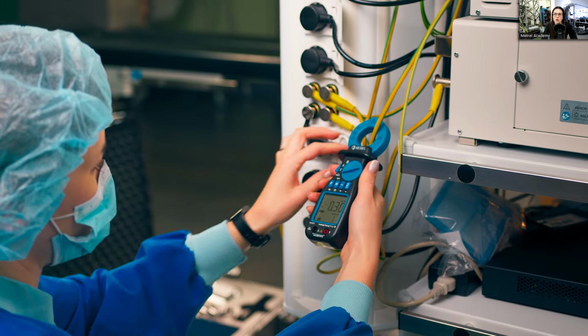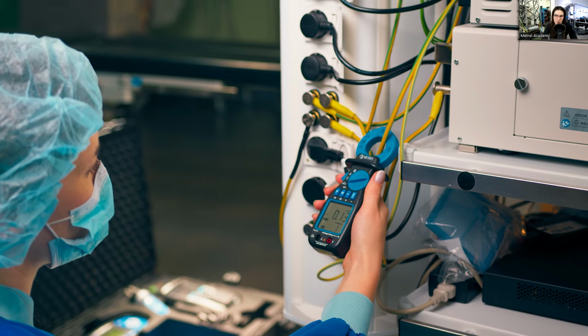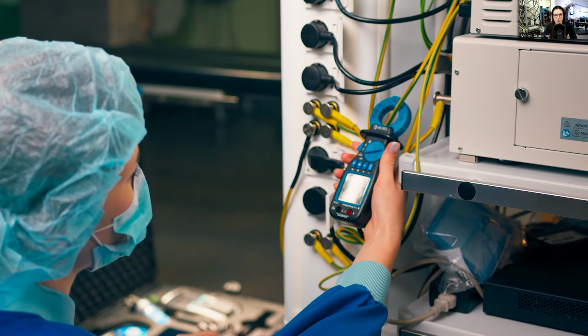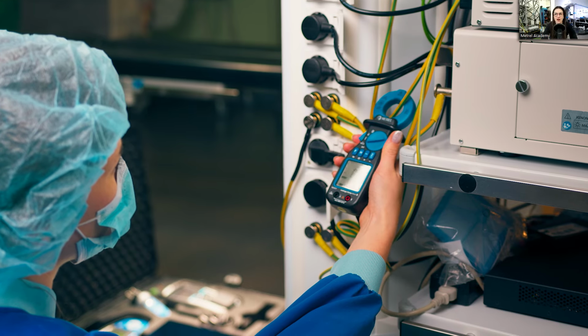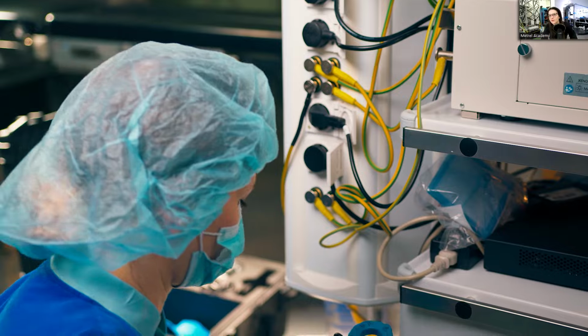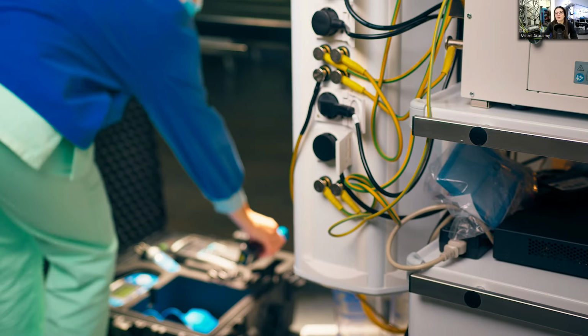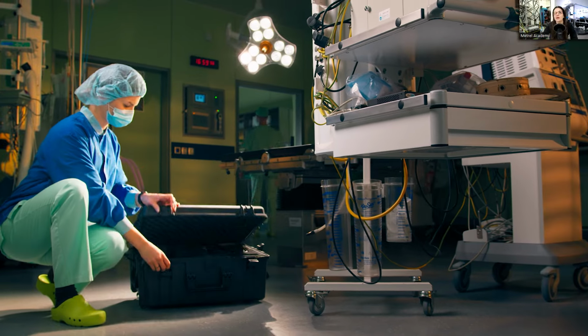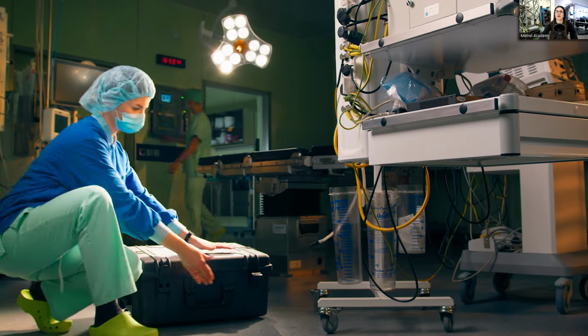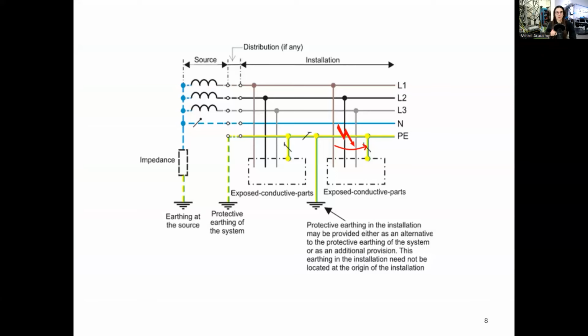Now, we have to find which of our devices is the source of the leak, and we do that by simply clamping each of the PE wires until we find the source of the leakage. So here in the background, we have the installation monitoring device. I wanted to show you this schematic, this diagram of the problem that I just described. So we have an installation failure in line 1 that causes a high leakage towards the PE wire. So here, this is our source of the problem.